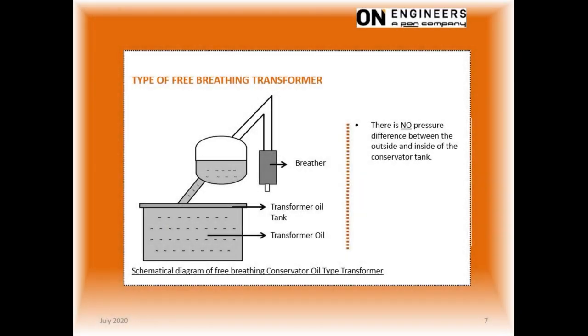This slide shows the construction of a breathing type transformer, which is used for the larger size transformer. This design will not create any pressure difference between the headspace inside the conservator tank and the outside air. The headspace is at the same pressure as the outside air. As the oil volume expands or contracts, the headspace will accommodate the oil expansion.